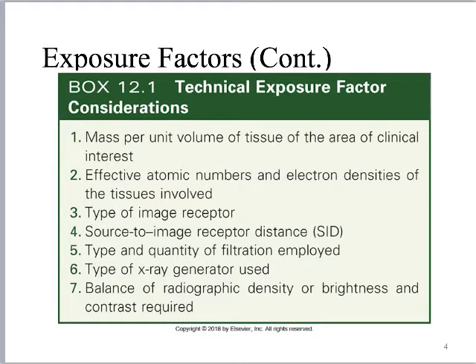Using different types of image receptors is a significant consideration. In the digital age, we see this when comparing photostimulable phosphor plate technology — what we used to call CR cassettes — versus digital imaging like indirect or direct digital imaging. For the most part, the DR, the newer cassettes, are going to decrease patient dose because they have a higher detective quantum efficiency. Increasing source to image receptor distance also decreases patient dose, following directly from the inverse square law.